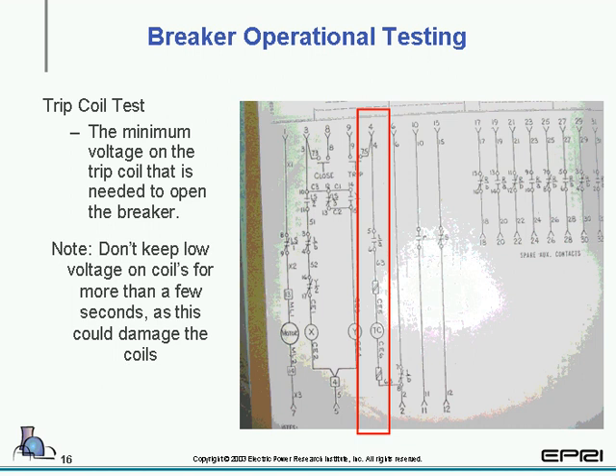Another way that you can do the testing is you can start off lower than 70, at 50% of the nominal voltage, or whatever your plant designates, and then run the voltage up by some value, 5 volts, if you will, and then push the close or trip button and let it go, and see if the breaker trips. And then continue doing that and make sure that it does trip at the minimum voltage, which is typically about 70% of the nominal.